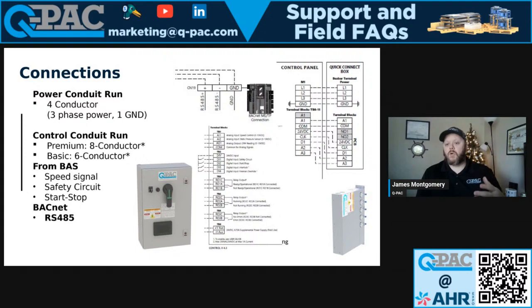Our team is currently working on ways to minimize how many wires we have to run, to make the installation easier. So we've actually recently gone from an 8 conductor on the premium to a 7 conductor. We eliminated one wire, just one at a time. We're trying to make this simpler, easier, and efficient for you. From the BAS: if you've got a BAS, you may have a speed signal, 0 to 10. That's going to go there.